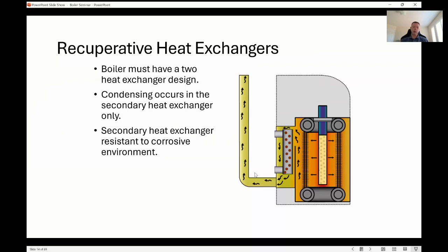That water vapor is going to go from a gas to a liquid, and you're going to grab that latent heat here. And then this heat exchanger is usually like a stainless steel or some kind of heat exchanger that's able to handle that acidic environment. From there, it goes to the primary heat exchanger, which is a non-condensing heat exchanger. Now, a lot of times, if you're in a modulating type appliance, you won't be able to get that guarantee that the inlet water temperature to the primary is above 130 degrees. So a lot of these products will actually have a built-in bypass that will take some of that hot outlet water from the primary and recirculate it back in, so you do not condense in that primary environment.